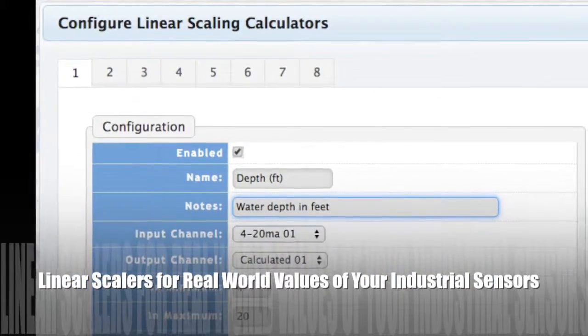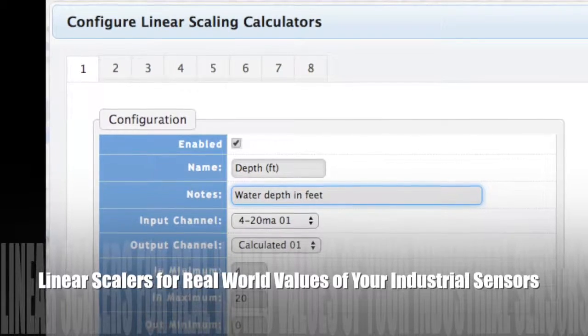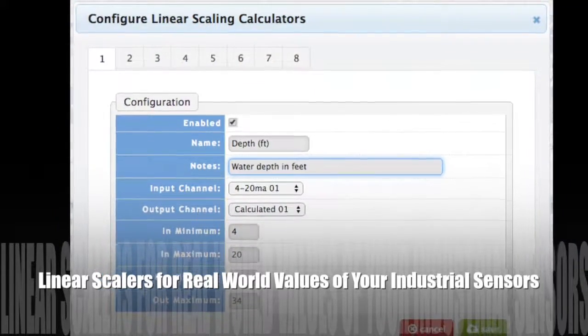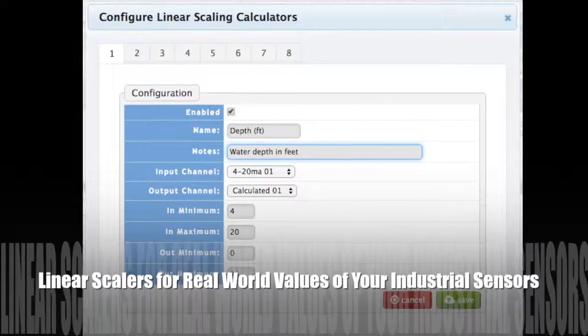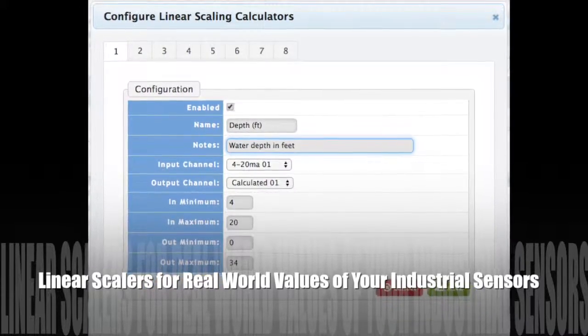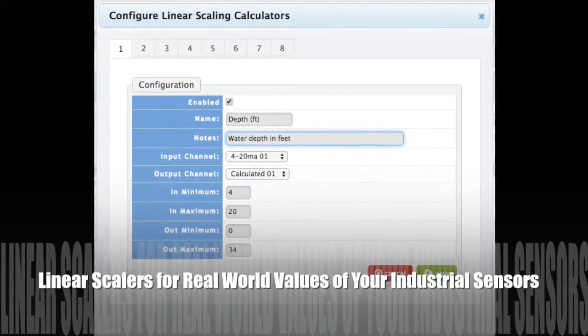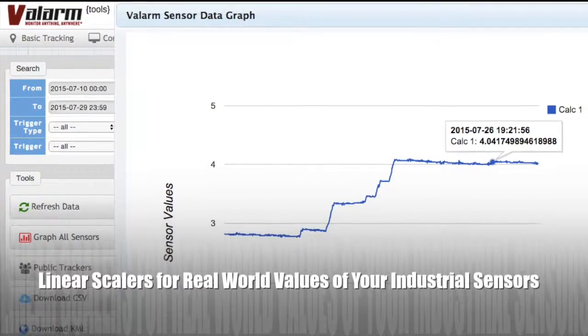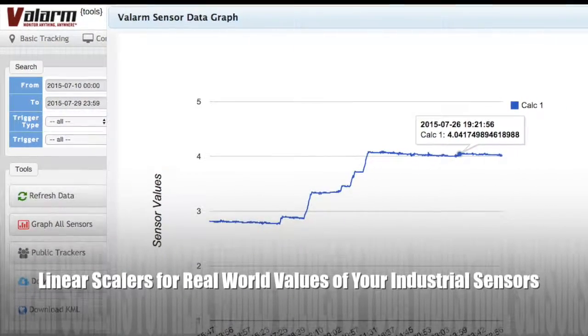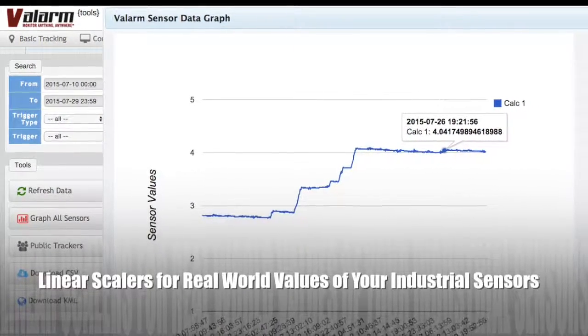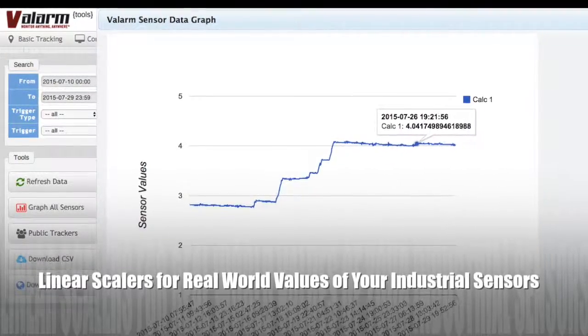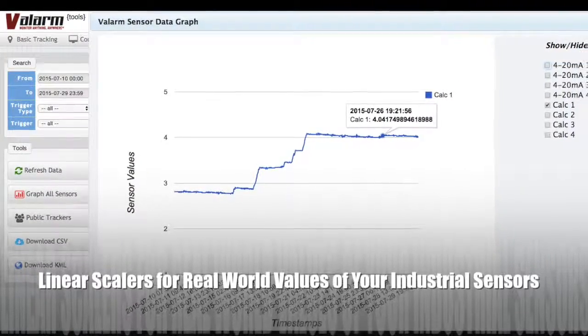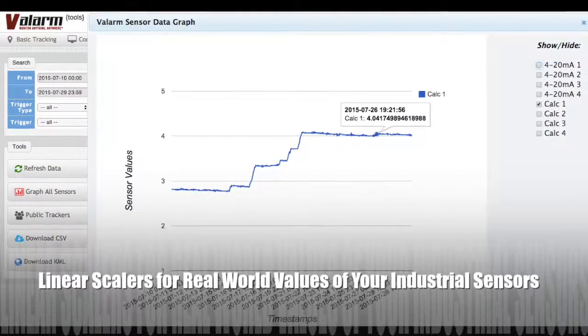With the linear scalers feature on tools.valarm.net you can set what your raw sensor's range is and what that corresponds to in real-world values. For example, perhaps your 0 to 10 volt air quality sensor scales from 0 to 500 ppm of a specific gas like ozone or nitrogen oxides.